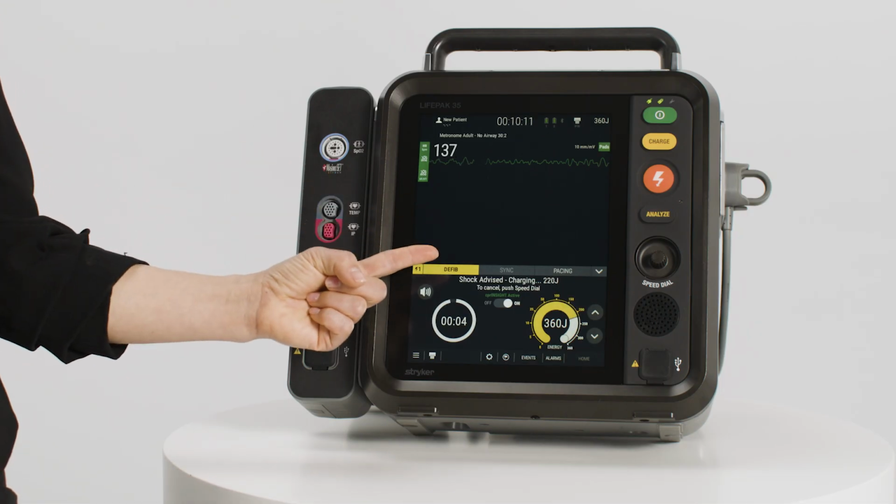Additionally, some LIFEPAK 35 devices may be configured to pre-charge in manual mode. If this setting is turned on, the device will begin charging near the end of the CPR time so that the device is ready to deliver a shock as soon as the CPR cycle ends. Charging indicators appear on the screen while the device is charging, and some devices may be configured to also include a charge tone.